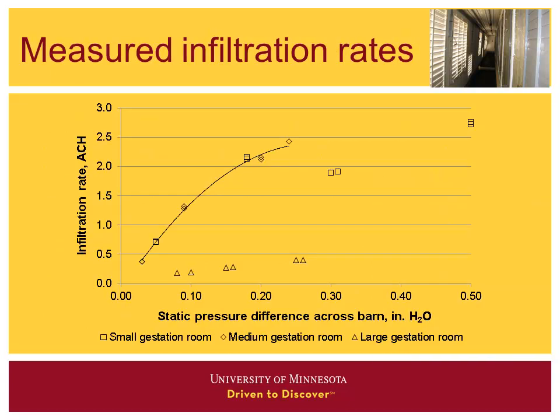Here's some of the data for those barns. There are diamonds and squares. The squares were a small gestation room of about 240 sows. A medium gestation room had about 3,000 sows, and then the large one had 5,000. The large gestation room was a very tight building, and we chose not to use that data for our analysis. The line shown is a polynomial that best fits the data for the 3,000-sow barn, and that's the relationship we're using between static pressure and infiltration rate in the model.